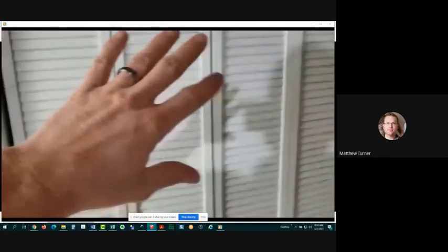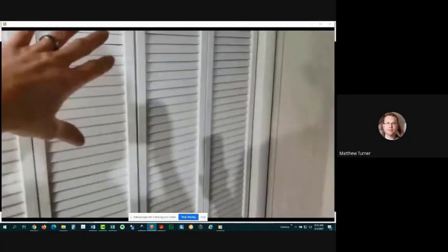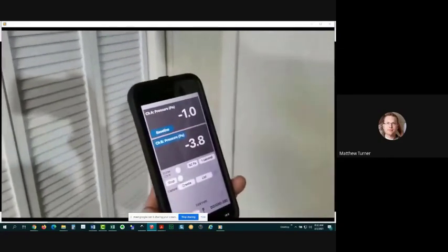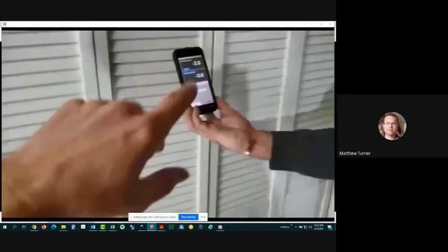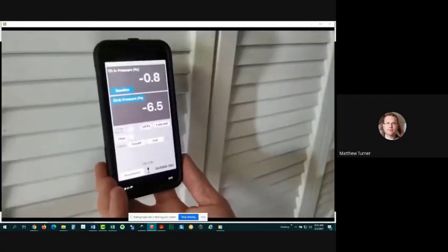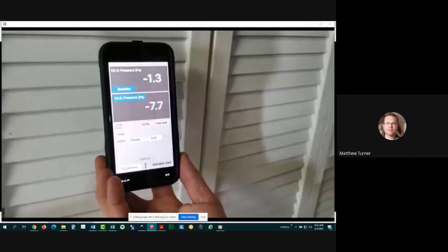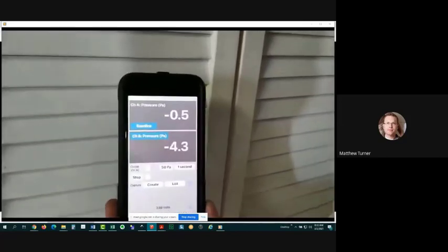Okay, because our CAZ actually has these louvered doors, we want to close them as well. So we are really considering these doors, this door over here, and the one behind the equipment. Those are all our CAZ doors, and we're supposed to start with them in a closed position. So we've set our manometer up inside here with all the hoses that I just showed you, but we've closed the louvered doors. Dalton's got his phone connected to that manometer through Wi-Fi so we can see what's going on. And again, on channel A, that's our CAZ pressure. It looks like it's bouncing around a little bit.